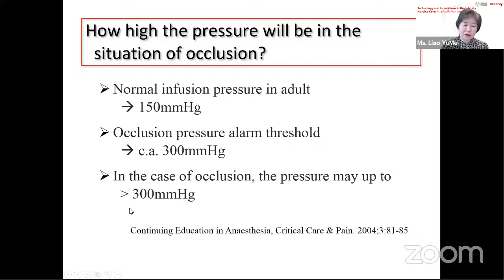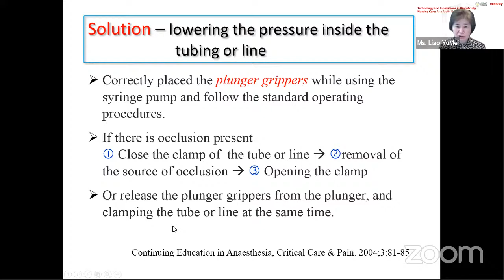We will use the syringe pump and follow the standard operating procedure. If there is occlusion present, we have a 3-step approach. The first step, close the clamp of the tubing or line. Second, remove the cause of the occlusion. Then open the clamp or release the plunger grippers from the plunger and clamp of the tube or line at the same time.